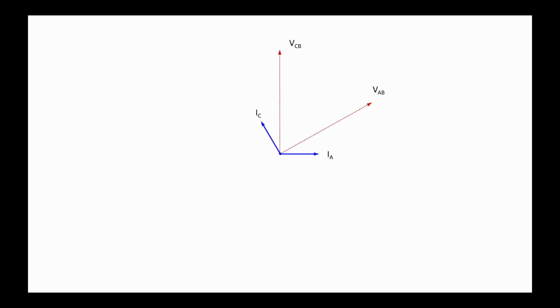Now we're starting to see a little bit of symmetry. These are my 2 single-phase wattmeter elements that produce watts based on the A to B voltage times the A phase current and the C to B voltage times the C phase current. And you'll notice in this diagram, remember we started with unity power factor, there was no phase angle between the voltage and the current in the Y-connected system we started with. So you'll notice that the part of the current which is in phase with the respective voltage is going to be additive, because both of them are in the same direction. They go in the direction of the voltage.